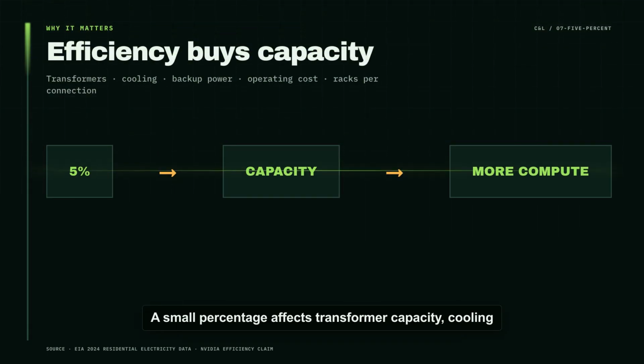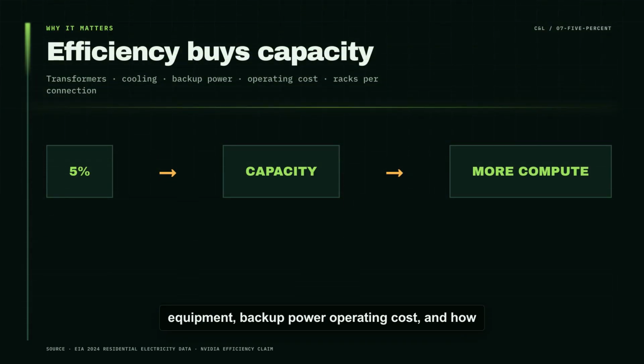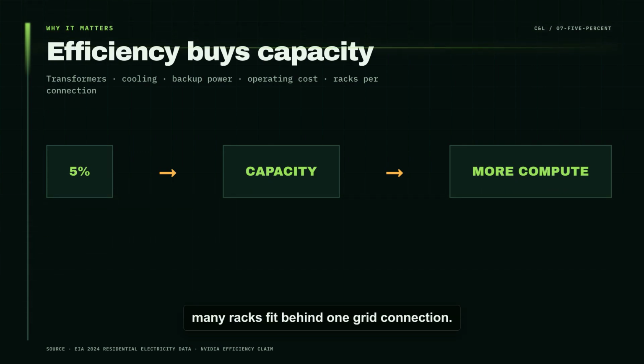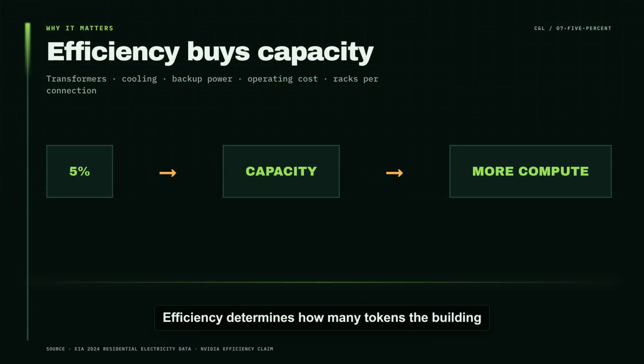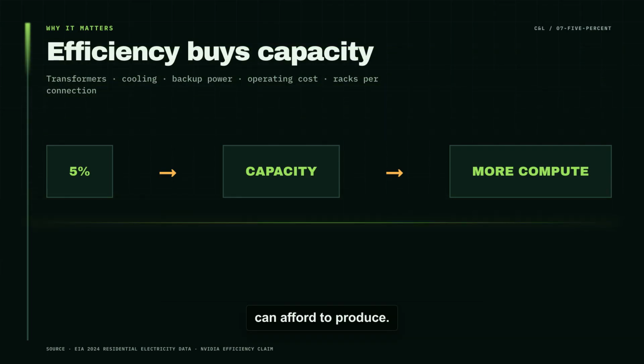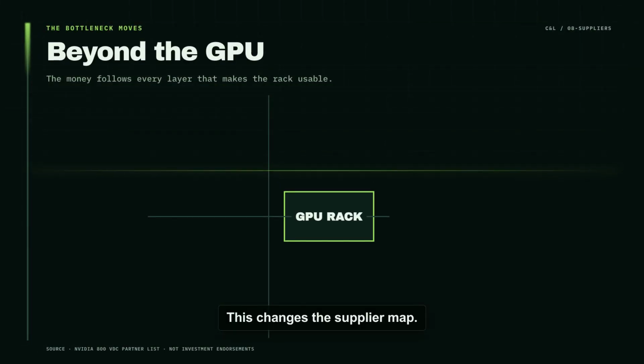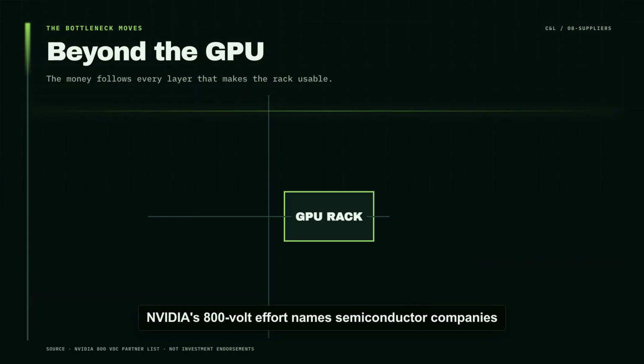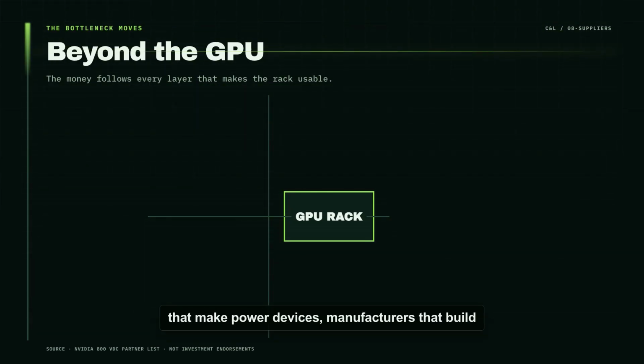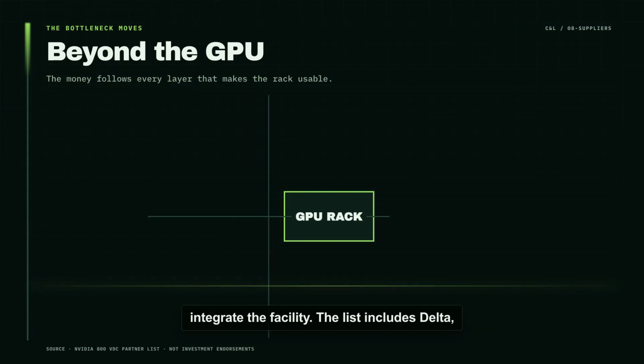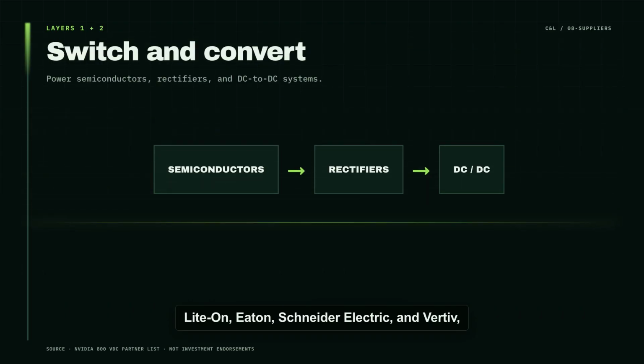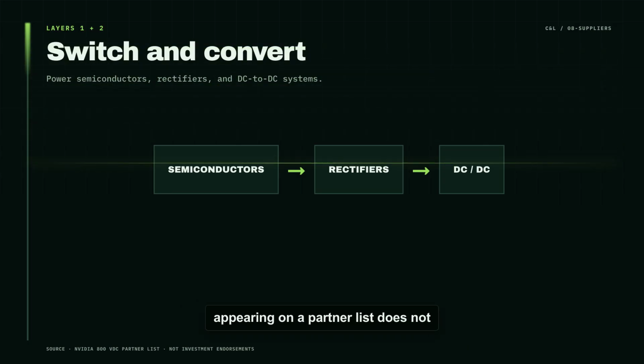A small percentage affects transformer capacity, cooling equipment, backup power, operating cost, and how many racks fit behind one grid connection. The chip makes the tokens. Efficiency determines how many tokens the building can afford to produce. This changes the supplier map. NVIDIA's 800-volt effort names semiconductor companies that make power devices, manufacturers that build conversion systems, and data center specialists that integrate the facility. The list includes Delta, Lite-On, Eaton, Schneider Electric, and Vertiv, among others. Their roles are different, and appearing on a partner list does not prove who will earn the best returns. But the categories tell us where the bottleneck is moving.